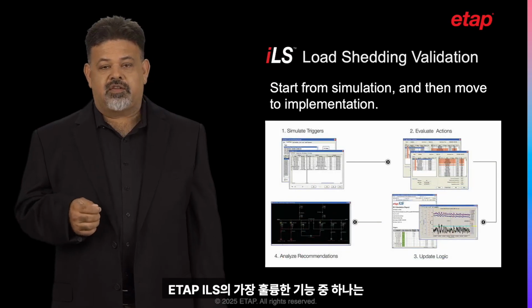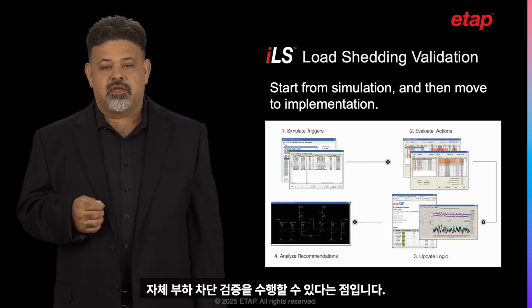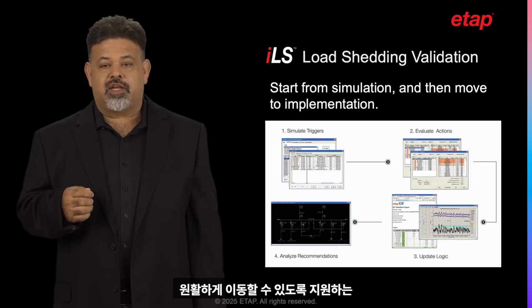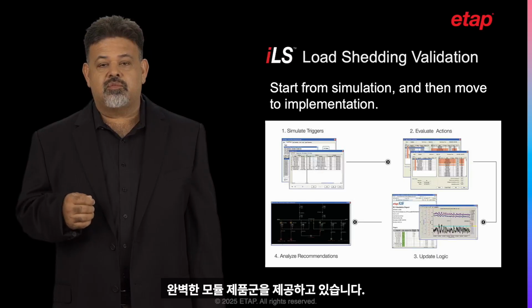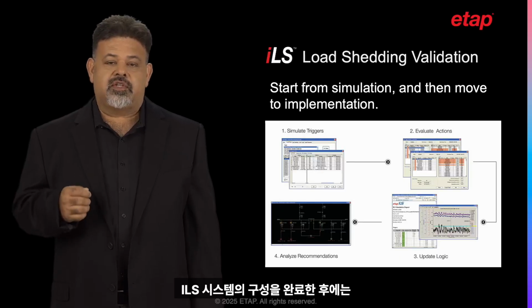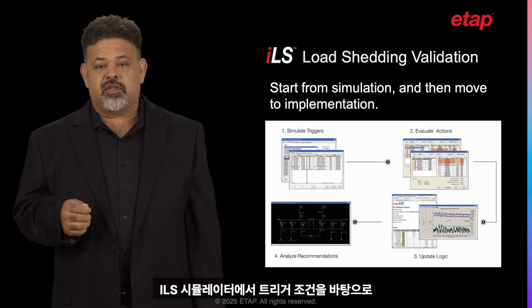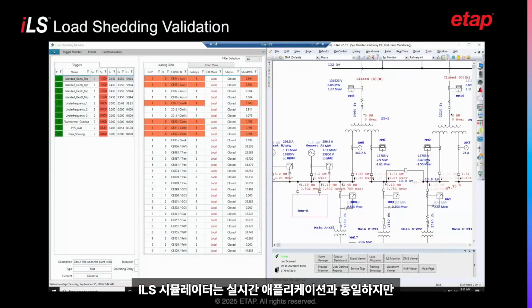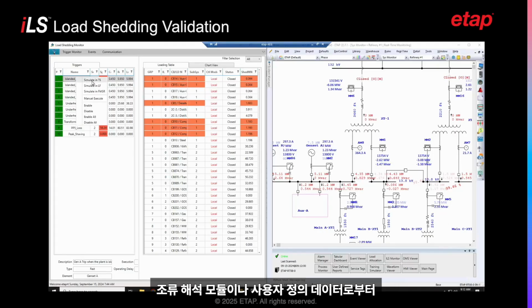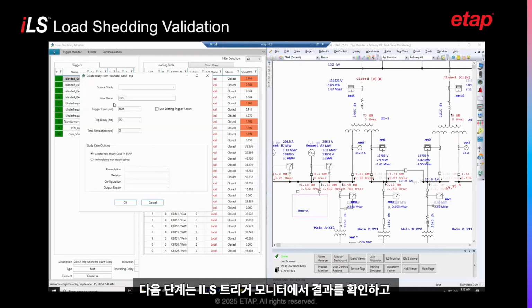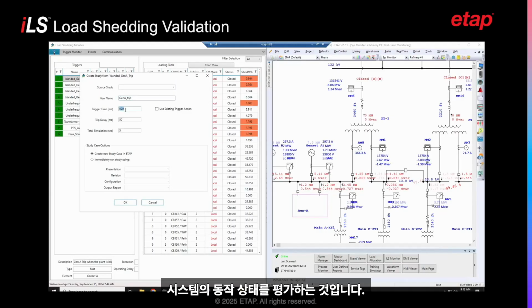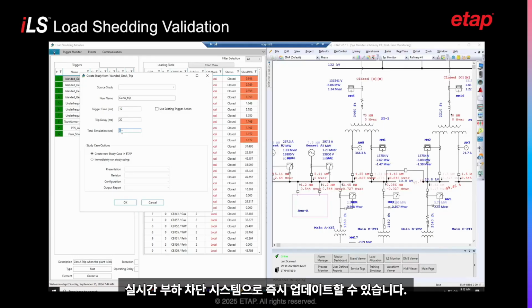One great feature of ETAP ILS is the capability to perform its own load shedding validation. ETAP ILS is a complete suite of modules that allows the user to start from simulation and smoothly move into implementation. After configuring the ILS system, the user can proceed to simulate the triggers in the ILS simulator. The ILS simulator is a duplicate of the real-time applications, with the exception that it can take data from the load flow module and from user-defined data. The next step is to evaluate the actions by viewing them in the ILS trigger monitor. Then they can be analyzed dynamically using the transient stability calculations. Once it is approved, the logic and priority tables can be updated to the real-time load shedding system.